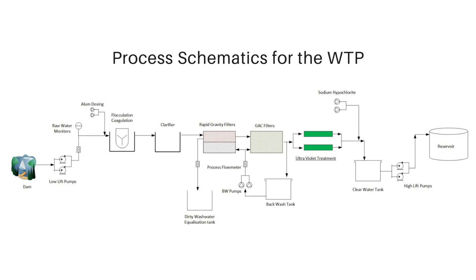As the water flows to the clear water tank we can dose sodium hypochlorite, which acts as a secondary disinfection. The purpose of this dose is that as the water is being transmitted within the network it will have free residual chlorine, ensuring that the treated water will not be recontaminated as it is pumped into the distribution network. We also have a backwash tank because as filters operate, their purpose is to trap dirt and particles.